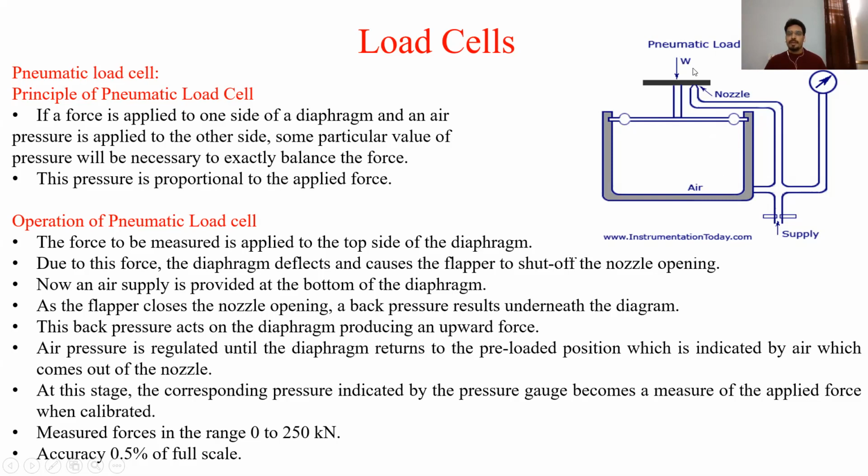And the measured force is in the range of 0 to 250 kilonewton. With the help of this pneumatic load cell, we can measure up to the range of 250 kilonewton, and the accuracy of this pneumatic load cell is 0.5% of the full scale. So this is how the pneumatic load cell works.